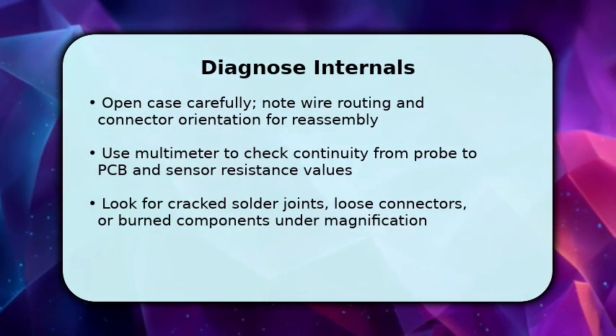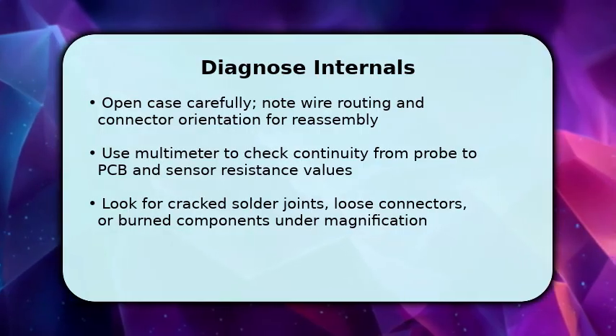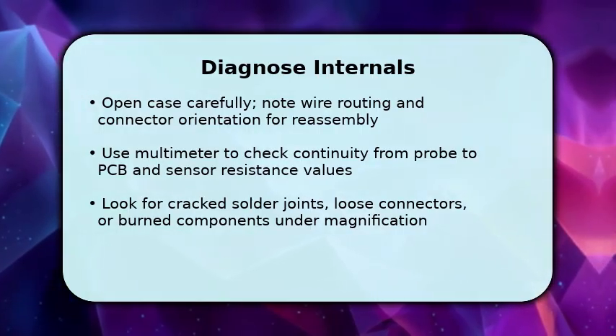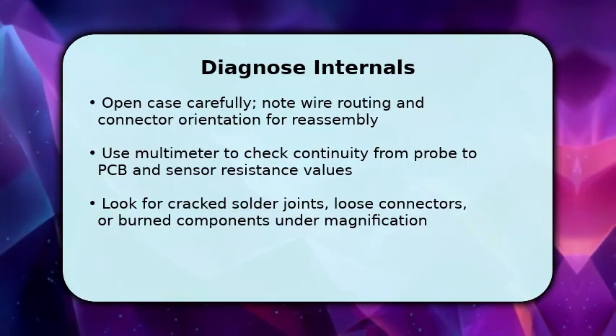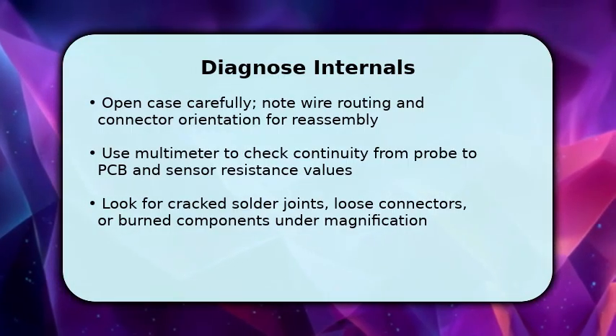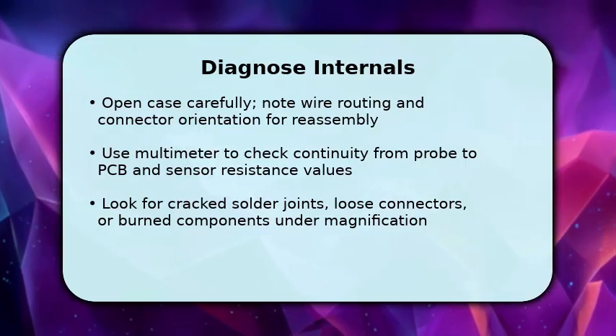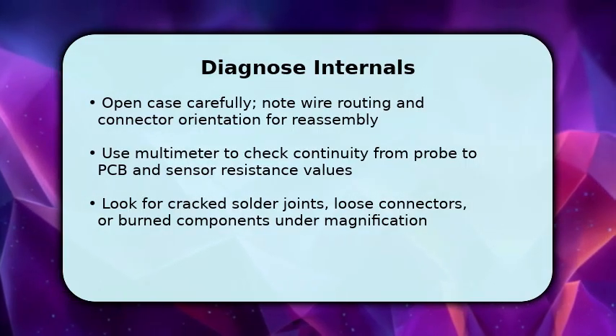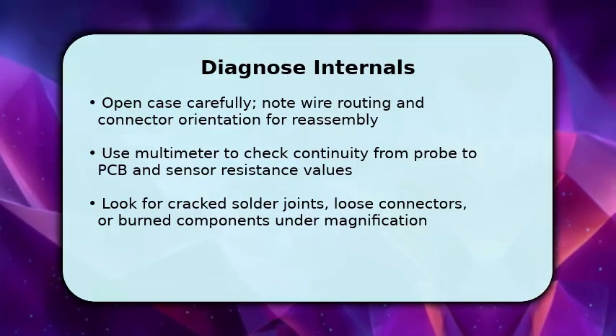Document wire routing and connector orientation with a photo so reassembly is exact. Then, using your multimeter, check continuity from the probe tip back to the PCB and measure the sensor resistance versus its expected curve. This tells you if the sensor itself failed.